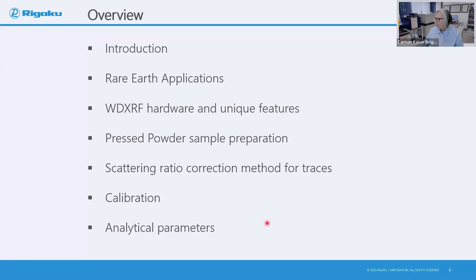As an introduction, XRF is used for the analysis of rare earth elements, for majors, minors, and trace elements in materials with a natural origin, and also for some industrial products containing rare earths. Commonly, we use ICP-OES or ICP-MS methods, but it's generally quite complicated, with extraction, acid digestions and daily calibrations. So we like to use XRF. Very often XRF is a more rapid technique where you can have a lot of sample throughput, and very advantageous is that we have a direct analysis of the solid material.